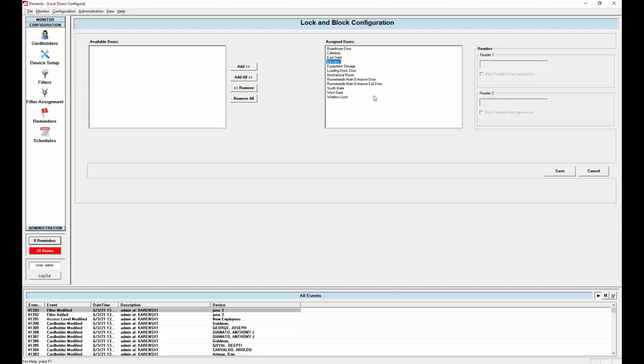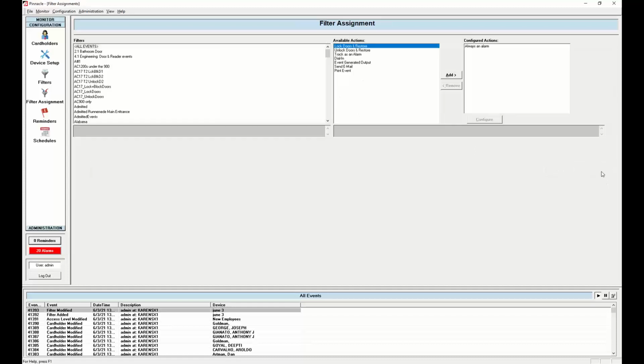The suggestion would be that the panic button be what we call a latching button, so that when your emergency is over and you restore that button to its normal position, the software then goes and checks all the time zones in all the controllers and puts the doors back into the state that they should be in right now, several hours after you went into lockdown, and not the state that they were in when the lockdown occurred, in case there was any time zone changes that occurred between the start of the lockdown and the resume to normal operations.